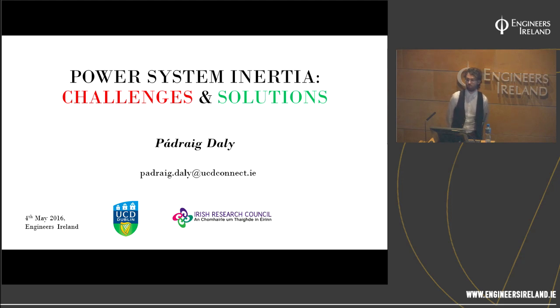The experience that we've had to date in how we are responding to dips in system frequency is that we're responding in a fraction of a second. So it's not really synchronous inertia, but it's what we might call synthetic inertia, and it is still valuable in terms of both rate of change of frequency and the nadir. So I don't know what your comment on that would be.